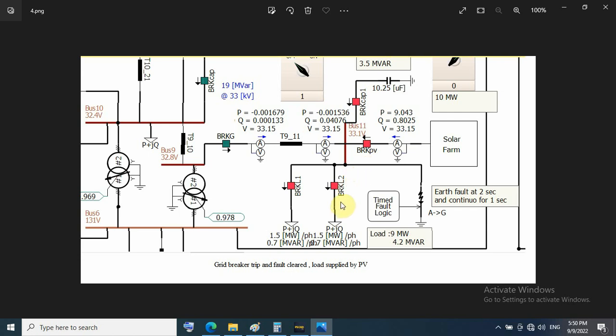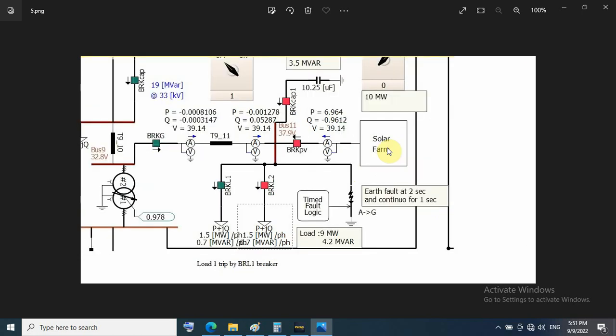But I don't know the scenario if this load is switched off - what will be the scenario? We will see it later. Here, this load is switched off without grid condition. Now the overvoltage is observed from PV side on bus 11. So in case of load switched off without grid connected to PV, overvoltage is observed, and the PV inverter should be tripped because of overvoltage.